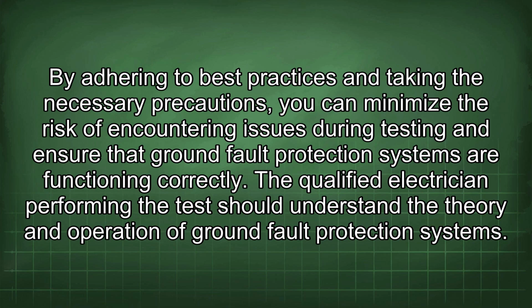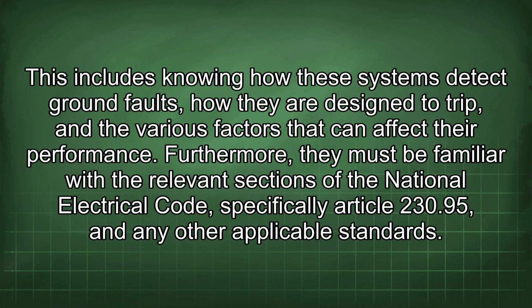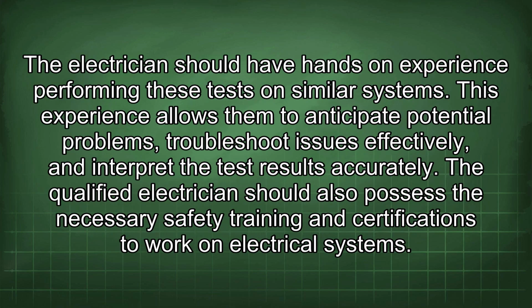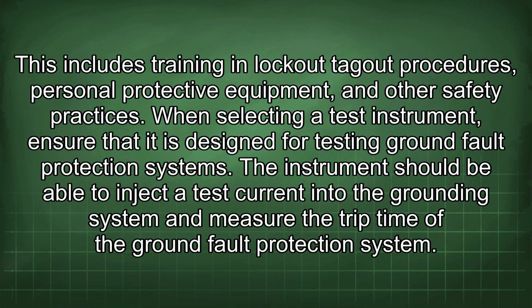The qualified electrician performing the test should understand the theory and operation of ground fault protection systems. This includes knowing how these systems detect ground faults, how they are designed to trip, and the various factors that could affect their performance. Furthermore, they must be familiar with the relevant sections of the National Electrical Code, specifically Article 230.95, and any other applicable standards. The electrician should have hands-on experience performing these tests on similar systems. This experience allows them to anticipate potential problems, troubleshoot issues effectively, and interpret the test results accurately. The qualified electrician should also possess the necessary safety training and certifications to work on electrical systems. This includes training in lockout-tagout procedures, personal protective equipment, and other safety practices.